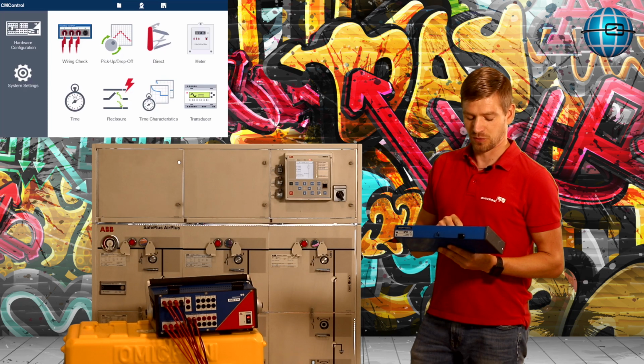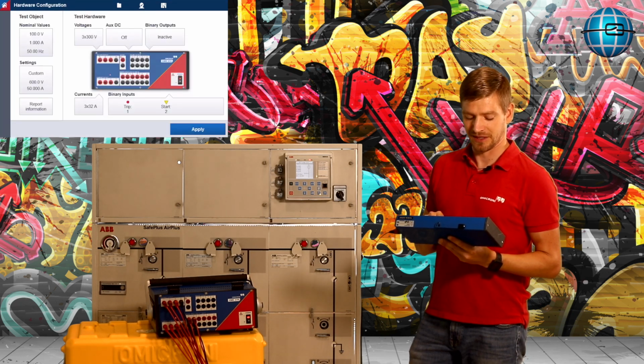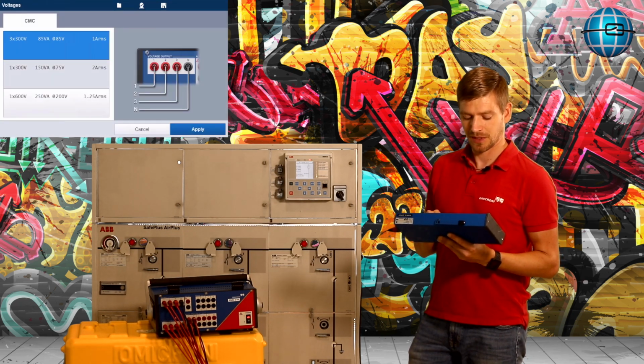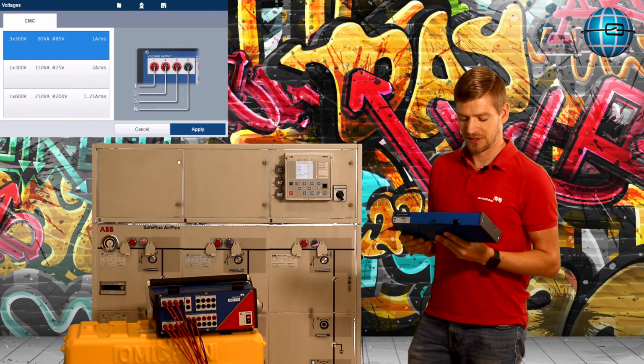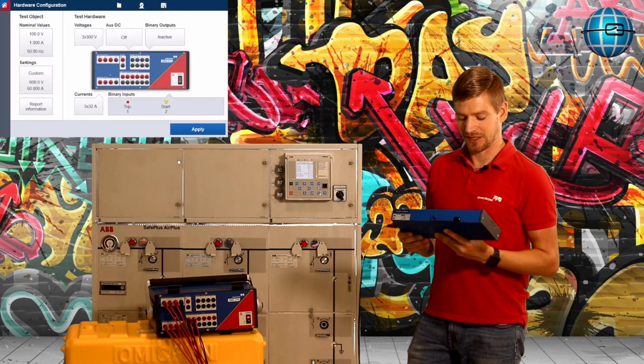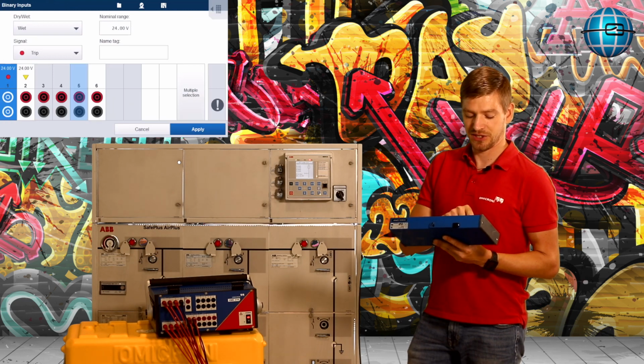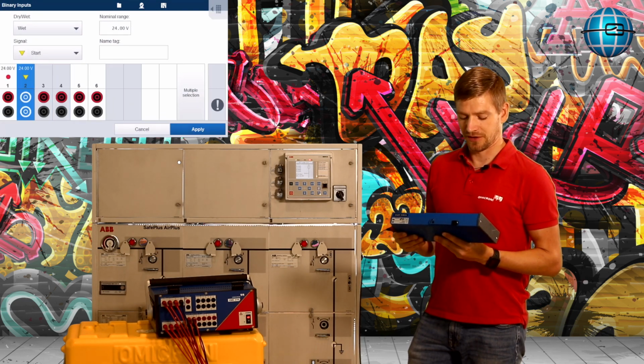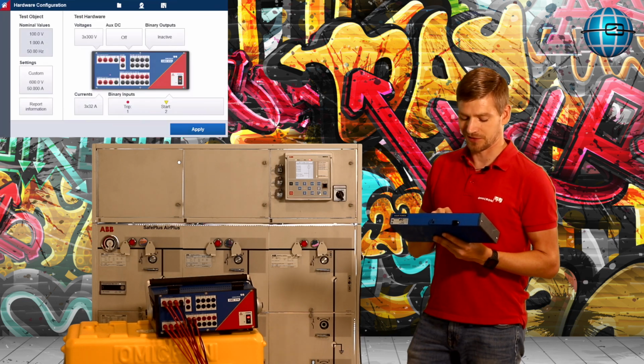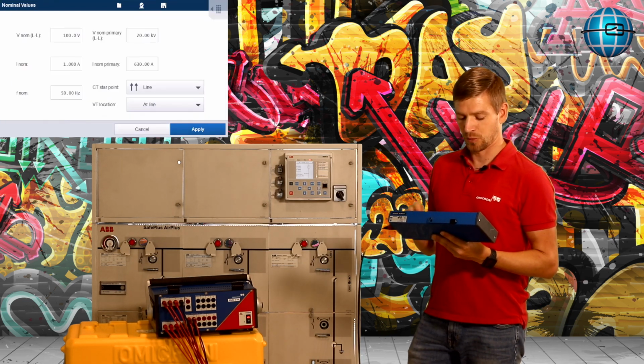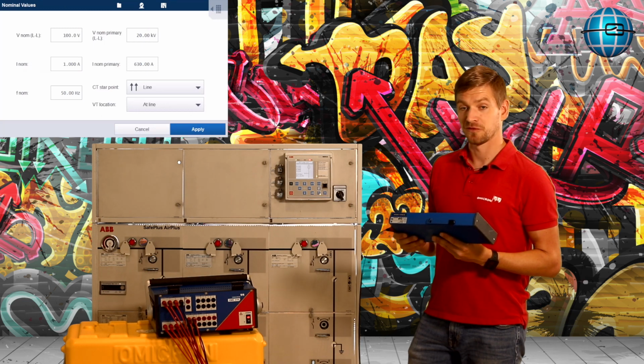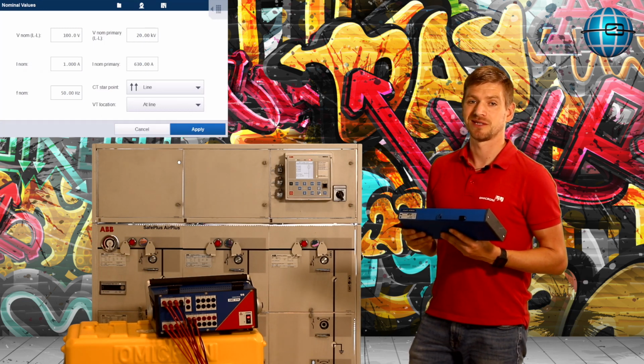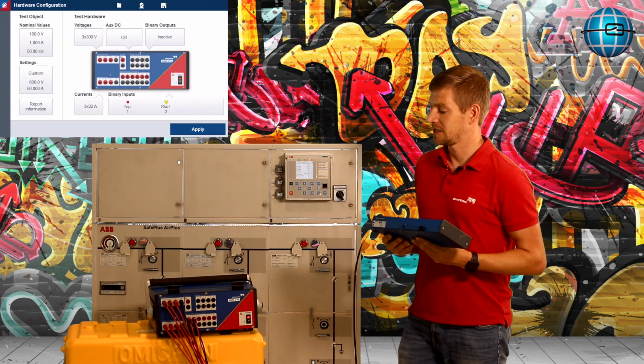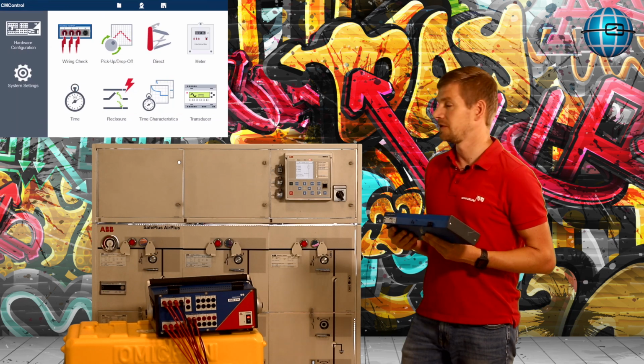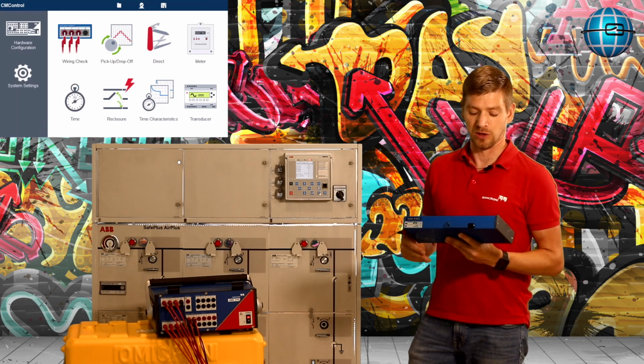So starting with the voltages, you can configure them here directly in CM control. And also the binary inputs, we have here a pre-configured trip and a start signal. In addition, you can also configure your VT and your CT settings. And when this is all configured, the first step we would recommend is a wiring check. With a wiring check, you can verify if your setup is wired correctly and if the ratio settings in your relay are also correct.